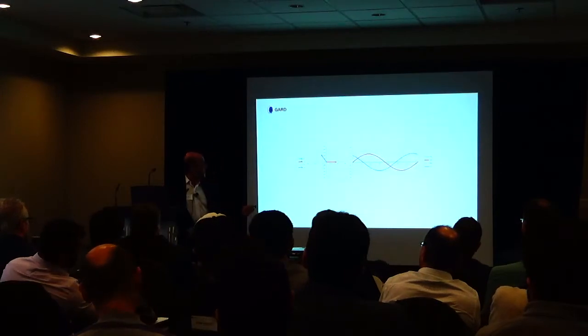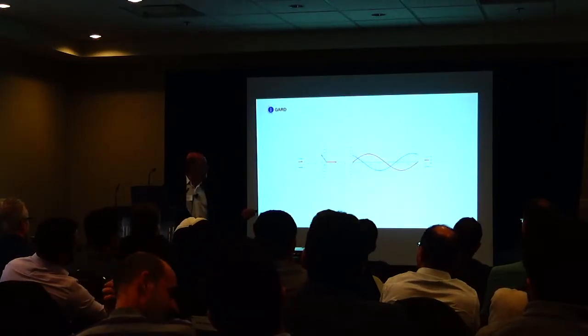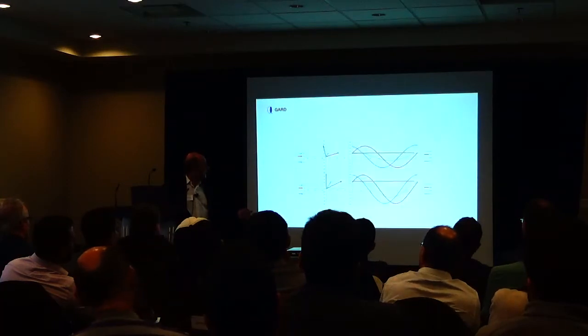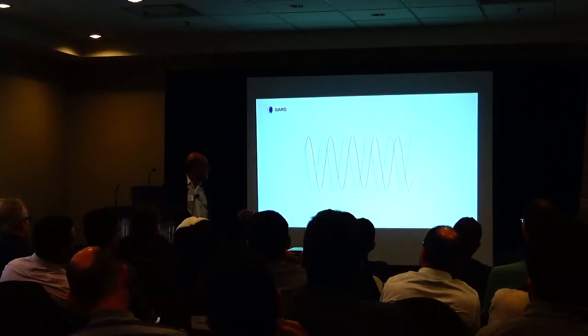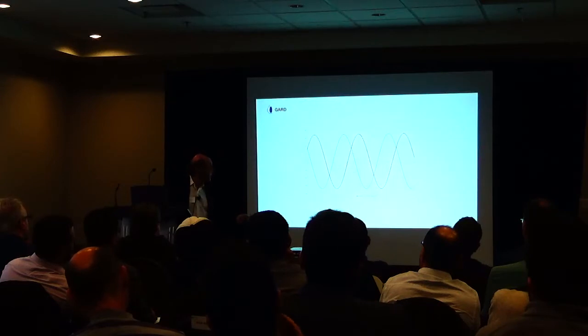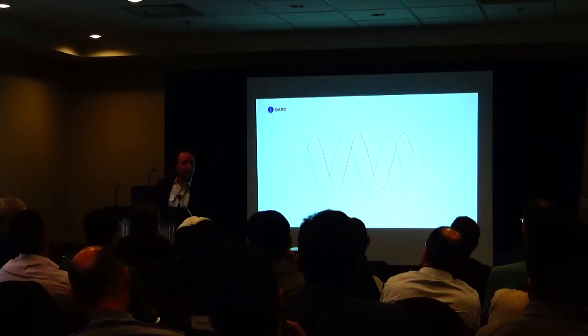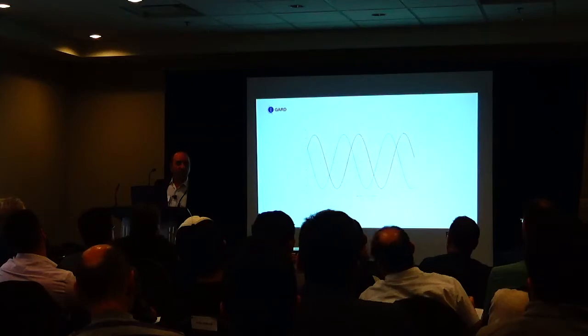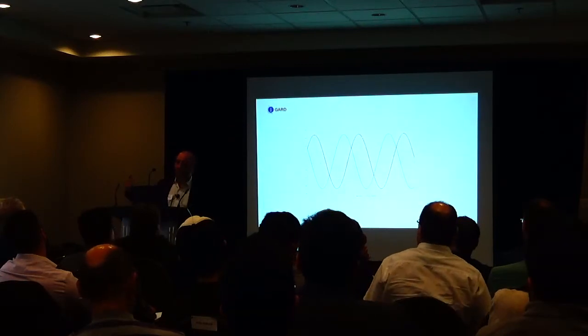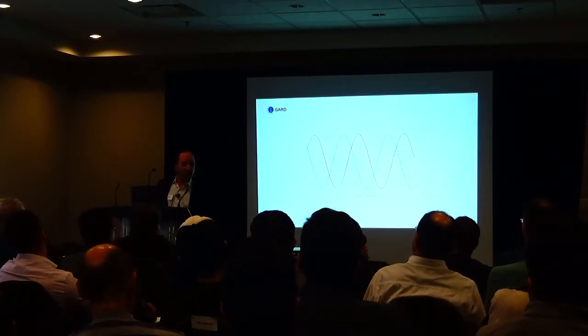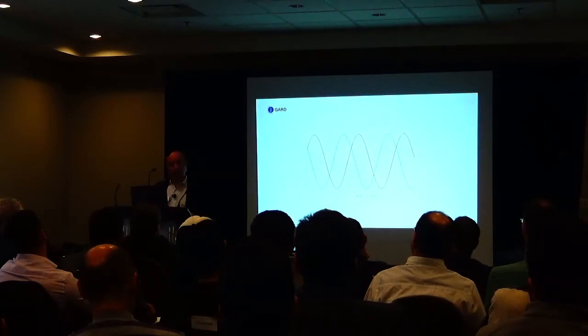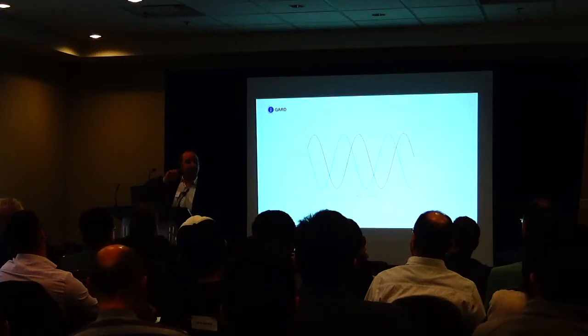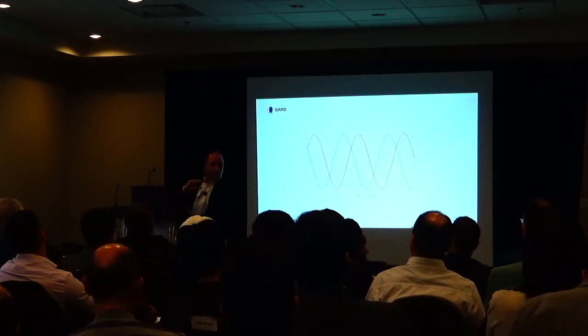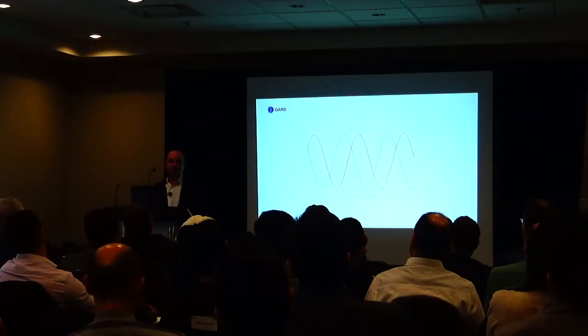This is normal. A, B, C, and that green line is neutral. This is the DC bus. So you have a fault on the output. Let's see, for example, when you have a fault on the output, let's assume your voltage and frequency is 50%. You want the motor to run at 50%. So now it's 60 hertz, you're running at 30 hertz. But you have to maintain the volts per hertz on the output of a variable frequency drive. So you're going to get half the voltage and half the frequency.